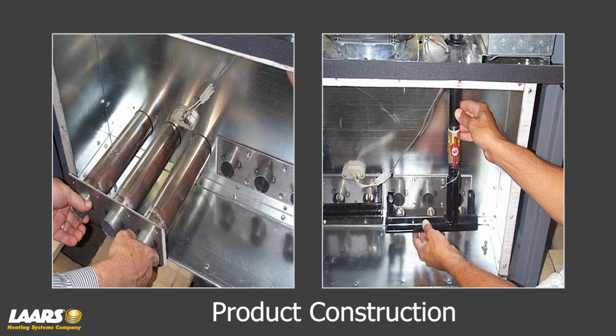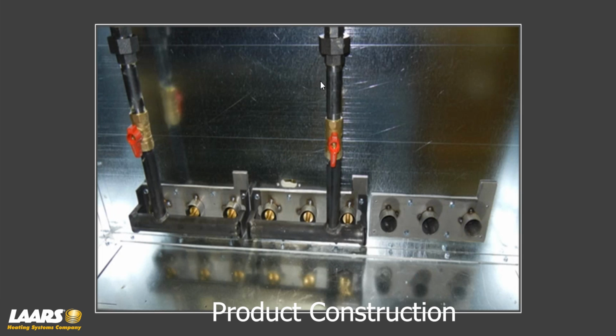And on your manifold are your orifices. Now, these products are available in both propane and natural gas. So you would have different orifices for LP or natural. The manifolds are held into position with 4 more stainless steel screws that actually bolt to the burner themselves. And now you'll see that the orifice is slightly recessed inside the burner. And this is just another image of a couple of manifolds being installed.